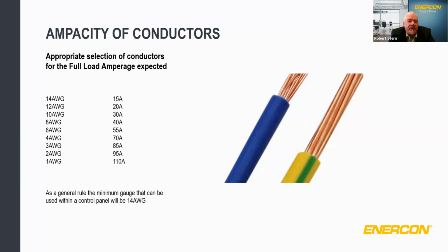Again, the full load amperage of loads intended to be connected by field wiring or to secondary sides of included transformers must also be carefully calculated for their amperage and ampacity. And when the load or FLA exceeds that wire gauge, you have to use the next highest wire gauge for that connection. The next page.